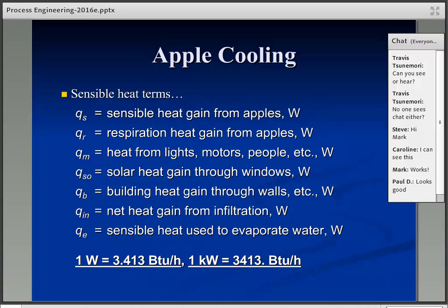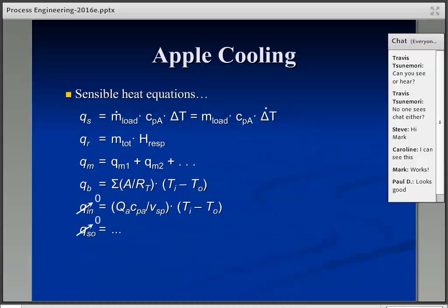Okay. This is a list of all those terms I just went over, so you'll have them, with unit conversion at the bottom. These kinds of problems, invariably you get some data in BTUs and your electrical data, and a lot of those mechanical loads are going to be in watts, so you've almost always got to go back and forth between watts and BTUs per hour on things like this. Even though I've shown all the terms as watts, the data might very well be in English units. So I just listed that.